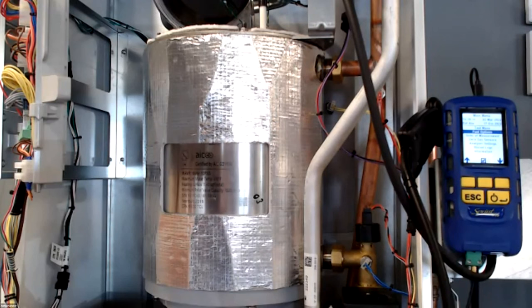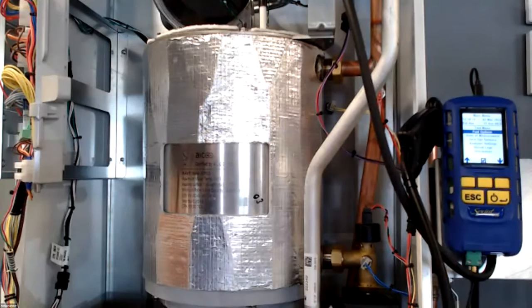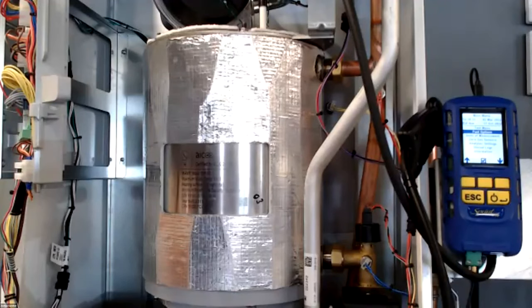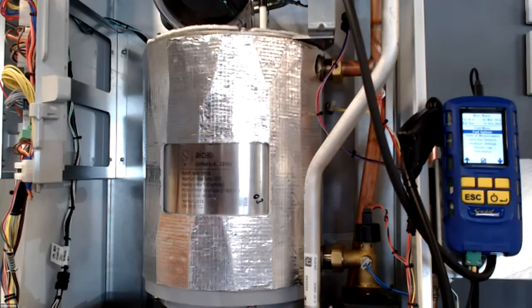You could use the CSST, but you're going to have to increase that quite a bit because of the restriction. And I'm not 100% against CSST. I used to rep a line, but it has its issues. But 5 feet to the regulator, too close. That's probably the problem. I would want at least 10 feet between the regulator and the boiler. I understand in some circumstances you can't get that 10 feet. It's real tough.